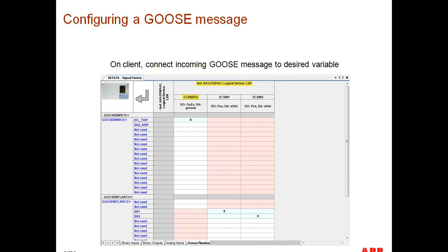In this particular case, this is just a view of PCM 600 where I'm showing that I am receiving this information. I'm receiving the position of breaker 1, I'm receiving the position of breaker 2, and then I associate that with different elements within my configuration. Again, this is not within the scope of 61850. This is within the scope of each individual relay as to how the relay will use that piece of information. So this could be SEL Accelerator, and how do you use that bit to affect logic inside of your relay. This could be EnerVista, as to, again, how do you use that bit as a piece of information to affect your logic inside of the relay. That's all we're doing here.